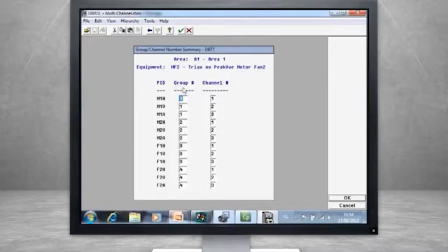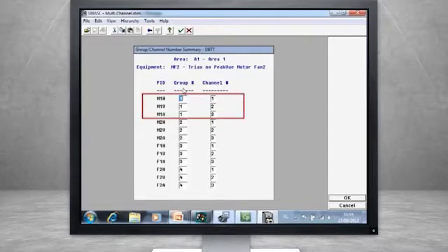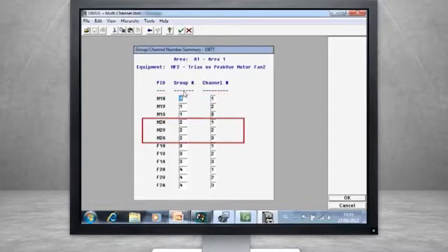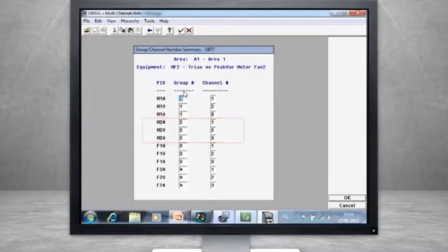In this example, we are working with a triax sensor, so we are able to have all three of the Motor 1 measurements in Group 1, Motor 2 measurements in Group 2, Fan Inboard measurements in Group 3, and so on.